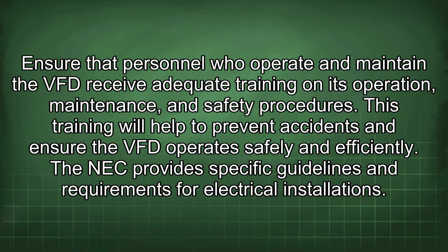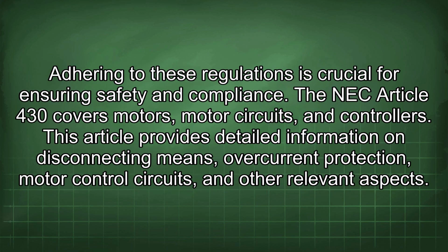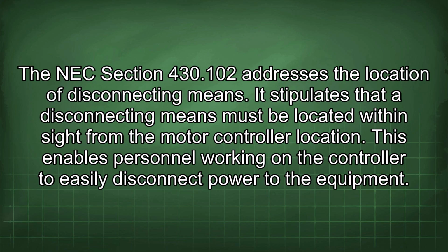The NEC provides specific guidelines and requirements for electrical installations. Adhering to these regulations is crucial for ensuring safety and compliance. The NEC Article 430 covers motors, motor circuits, and controllers. This article provides detailed information on disconnecting means, overcurrent protection, motor control circuits, and other relevant aspects. The NEC Section 430.102 addresses the location of disconnecting means. It stipulates that a disconnecting means must be located within sight from the motor controller location. This enables personnel working on the controller to easily disconnect power to the equipment.